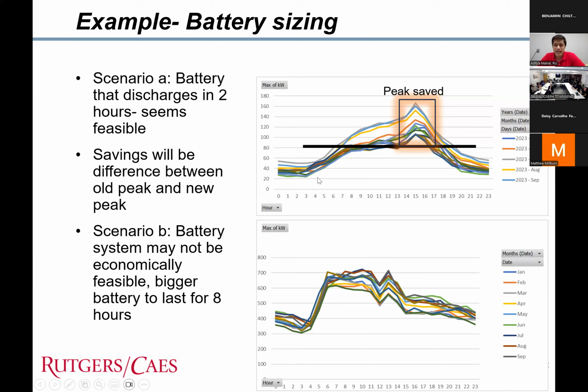Now, in the second case, I'm not saying it's not feasible - it's just that the economics will shift. Now we want the same 80 kilowatt battery to last for 8 hours, so we need about a 640 kilowatt hour battery. Multiplying that with $500, the cost goes high, but maybe their demand charges are high enough to justify that.